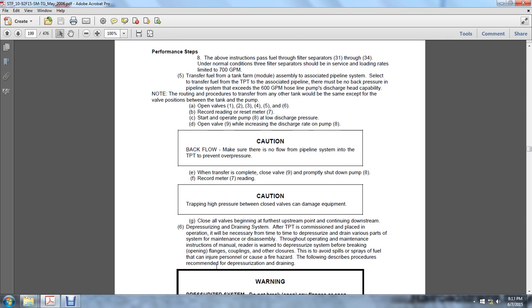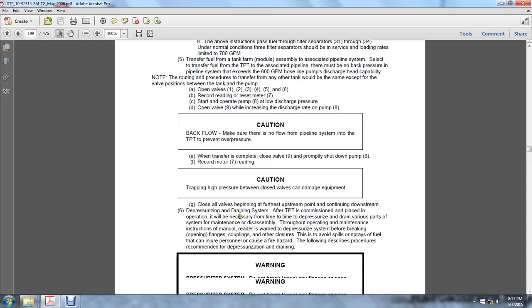Depressurizing and draining system: after the tactical terminal is commissioned and placed into operation, it will be necessary from time to time to depressurize and drain various parts of the system for maintenance and disassembly. Throughout the operating and maintenance instruction manual, the reader is warned to depressurize pressurized systems before breaking open flanges, couplings, and other closures. This is to avoid fuel spills that can injure personnel and cause fire hazards. Follow the procedures recommended for depressurizing and draining.